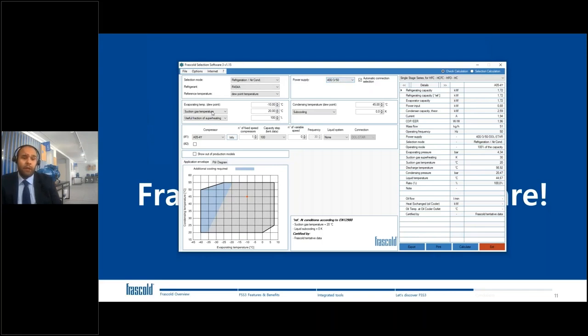Then the suction condition, in which you can set the evaporating temperature here, and the next two boxes to set the suction superheating. Here you can set the suction gas temperature directly, or set the suction superheating directly. The information is the same. You can set the superheating or directly the suction temperature, the information is the same.